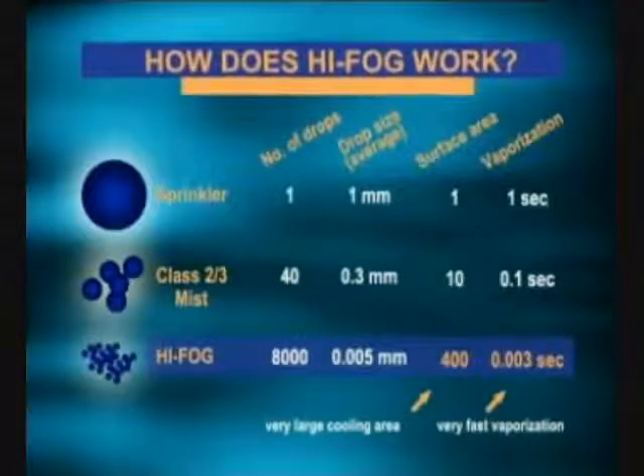It is here that we find an interesting phenomenon and a key to the efficiency of water mist systems. Because water mist systems produce 40 droplets of water in the same space as one drop of sprinkler water, the combined surface area of these 40 droplets is actually 10 times that of a sprinkler droplet. Therefore, the cooling effect is also increased by a factor of 10. With a HI-FOG water mist system, the system pressure is further increased and the water droplet size is reduced even more. In fact, HI-FOG systems are able to produce 8,000 droplets of water in the same space as our single drop of sprinkler water. These 8,000 droplets have a combined surface area increased 400 times, resulting in a corresponding increase of the cooling effect by 400 times that of a traditional sprinkler system.